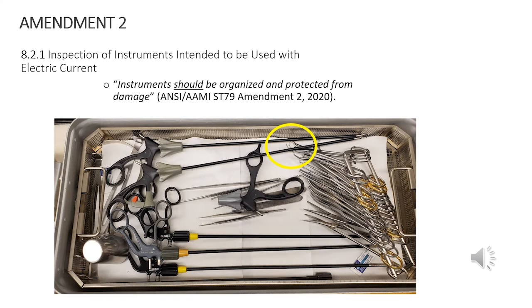In the new section, 8.2.1, under Inspection of Instruments Intended to be Used with Electric Current, it states that instruments should be organized and protected from damage. As you can see here, the tray looks really organized. The issue lies when you have metal, as you can see where it's circled, where the towel clips are scraping against the insulation of those shafts. So it really helps to have your insulated items separated from your metal instruments.